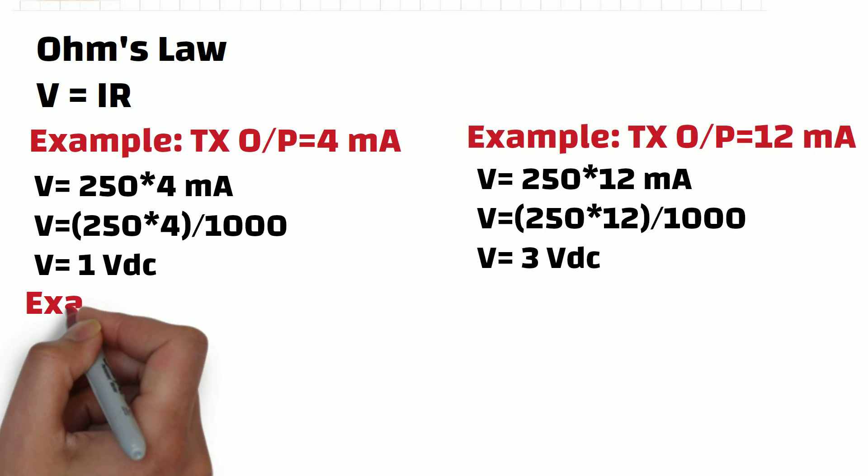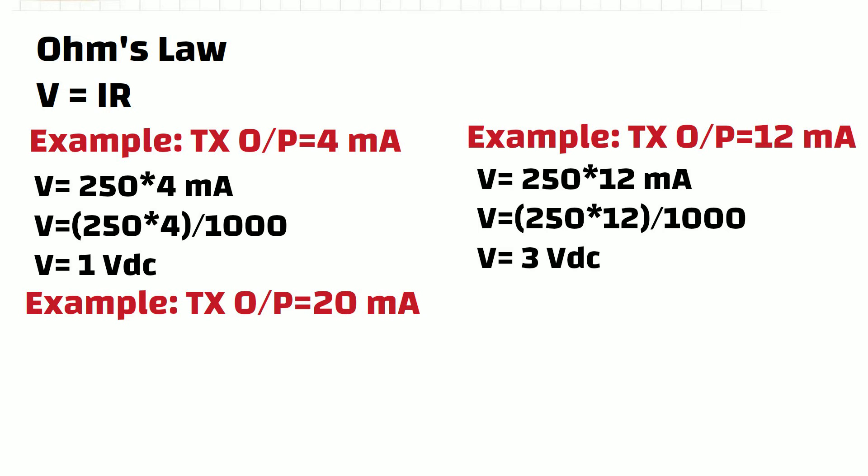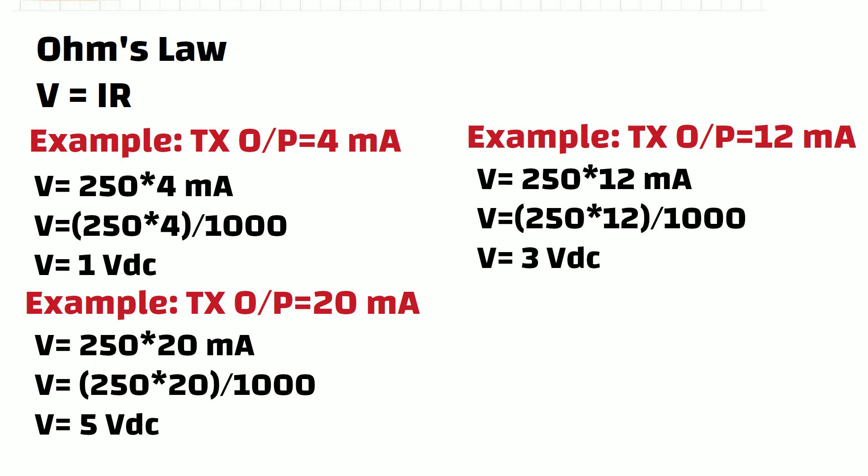Let's take one more example. Let's assume that transmitter's output is 20 mA. Now, put 20 mA and 250 ohm into equation, and do the simple math calculation. You will get 5 volt DC as a result.